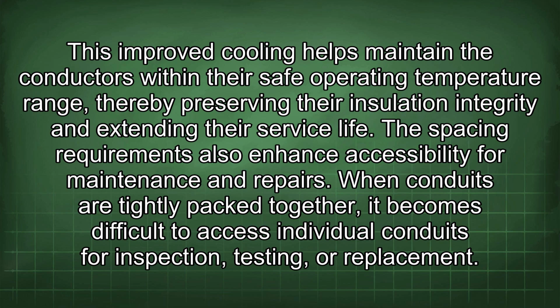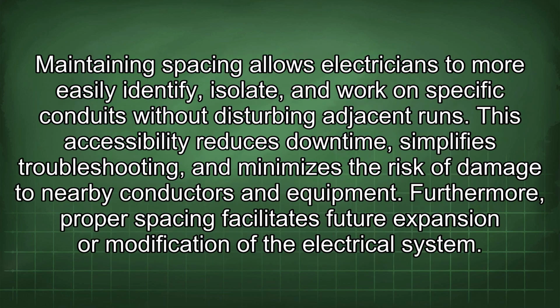The spacing requirements also enhance accessibility for maintenance and repairs. When conduits are tightly packed together, it becomes difficult to access individual conduits for inspection, testing, or replacement. Maintaining spacing allows electricians to more easily identify, isolate, and work on specific conduits without disturbing adjacent runs. This accessibility reduces downtime, simplifies troubleshooting, and minimizes the risk of damage to nearby conductors and equipment.